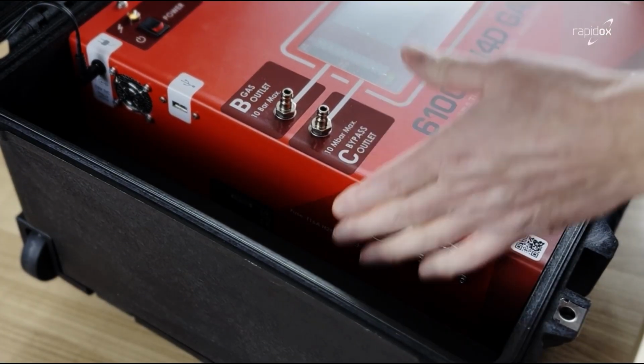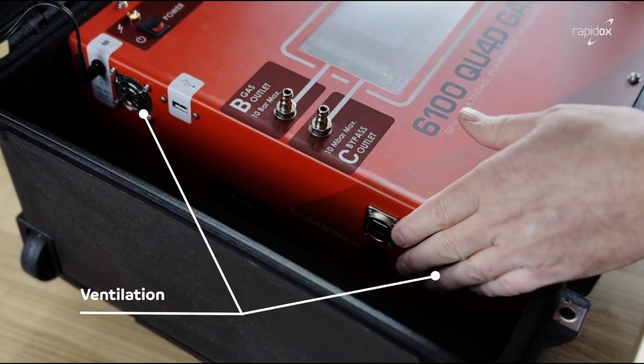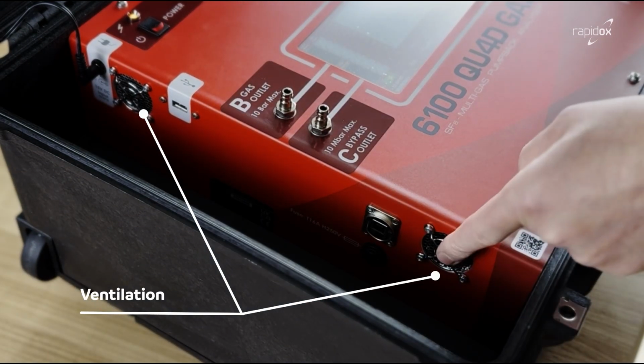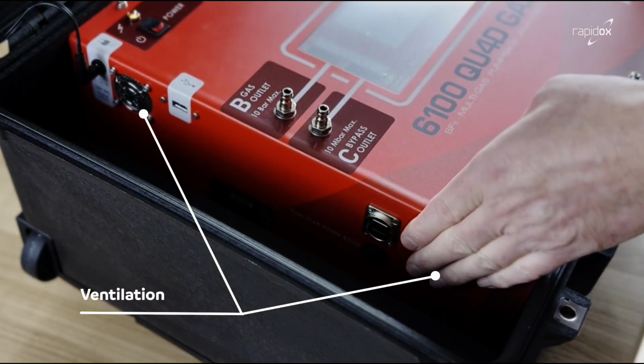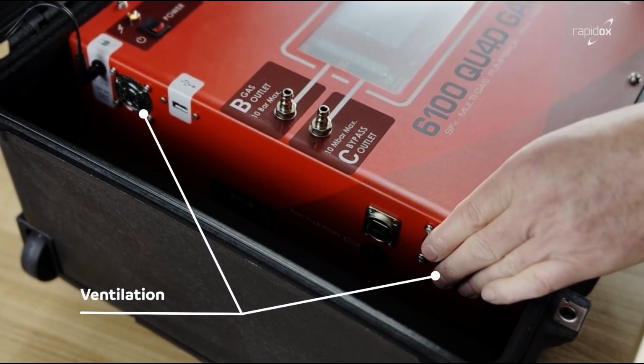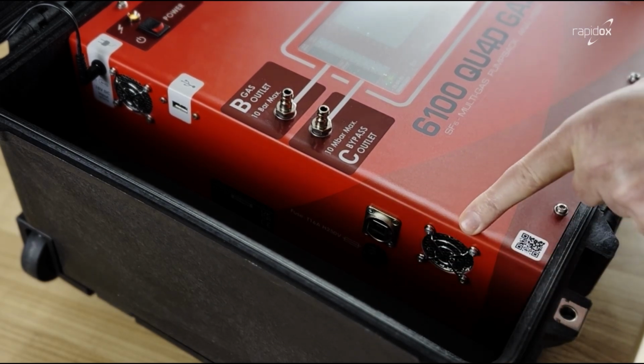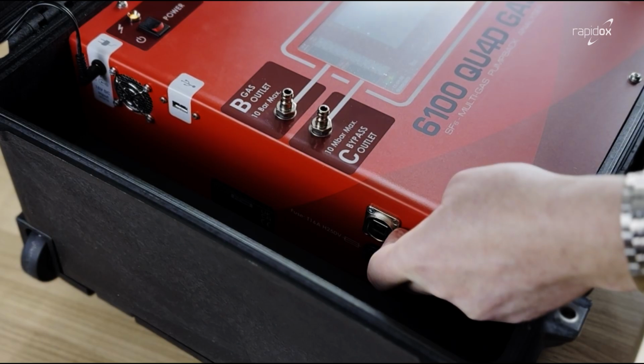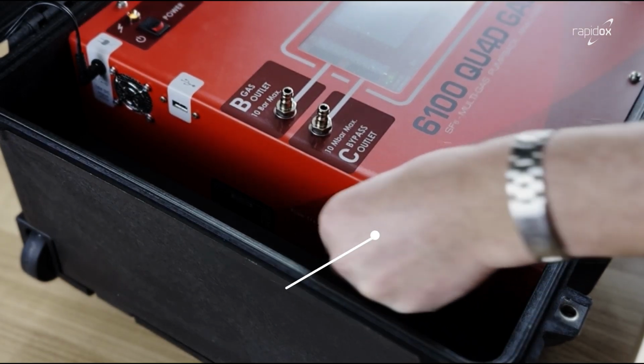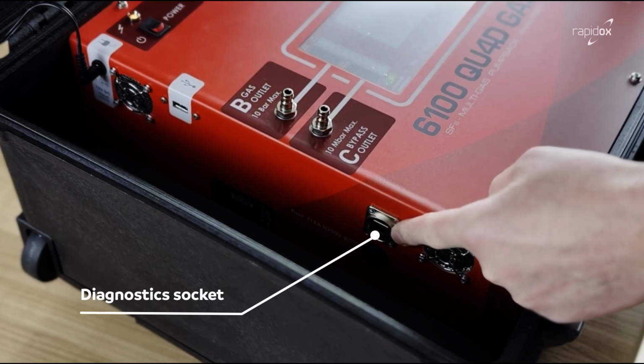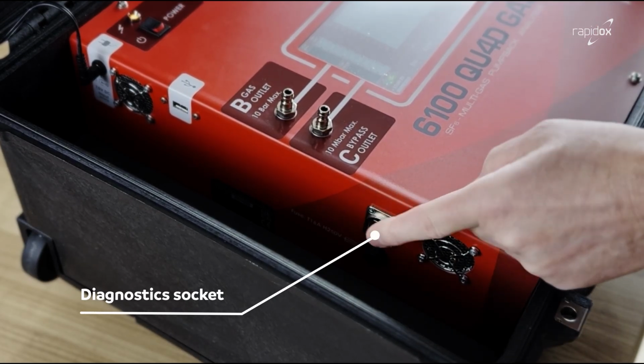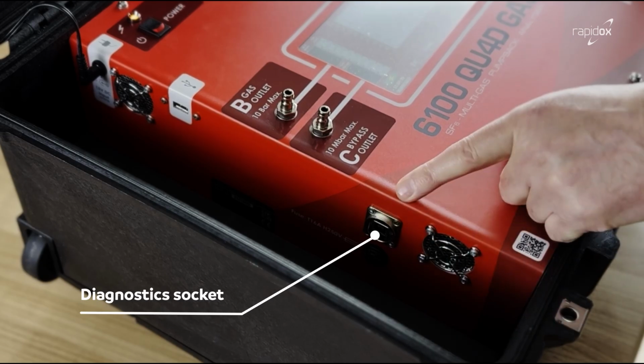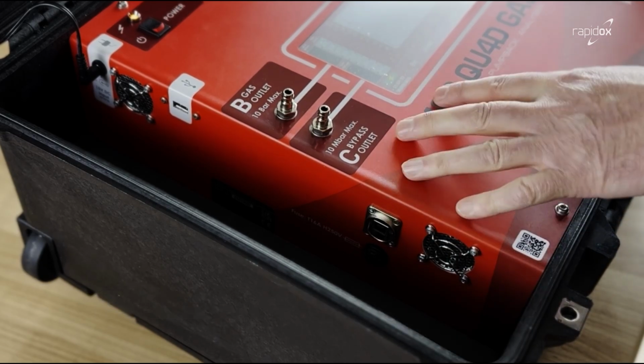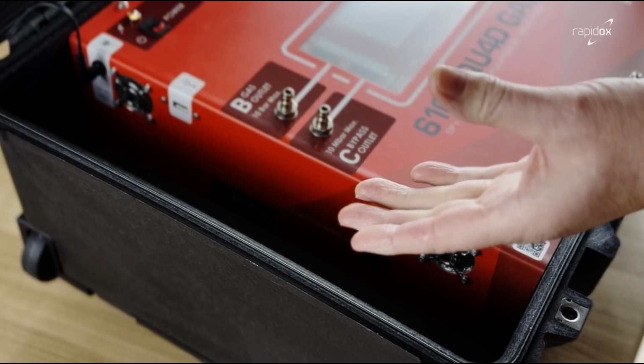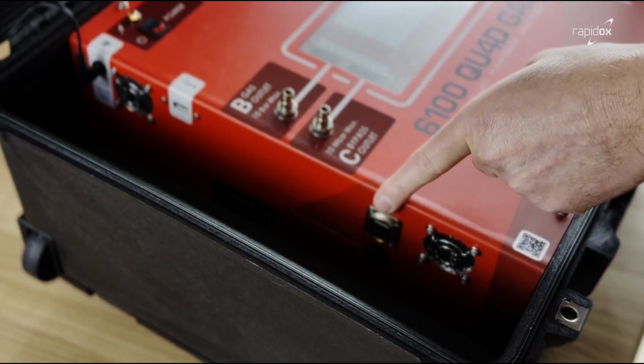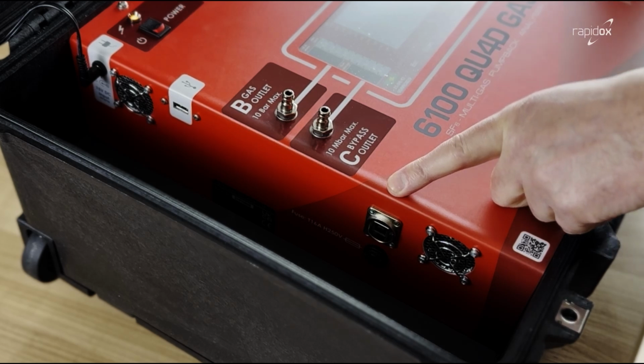Moving round to the folded section of the analyzer, there are some additional features here in addition to the charger. So we have two ventilation fans, and there are fans in this to circulate fresh air inside the analyzer. Now, alongside these, we've got two things that are very important. One is a diagnostics socket here. This is normally used here in our factory to program the analyzer, but it can also be used by the customer to help us connect this analyzer, for example, directly to a laptop computer. So this port here isn't normally used unless there's maintenance issues.